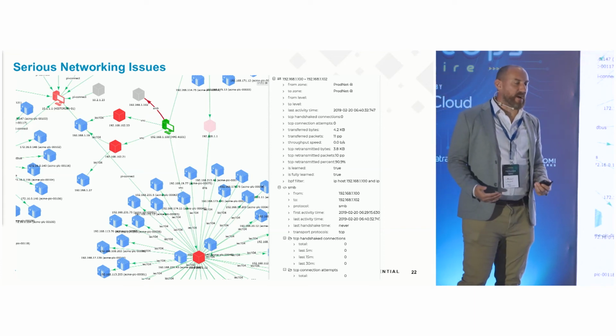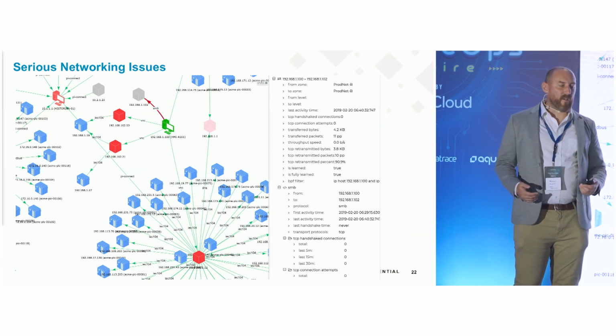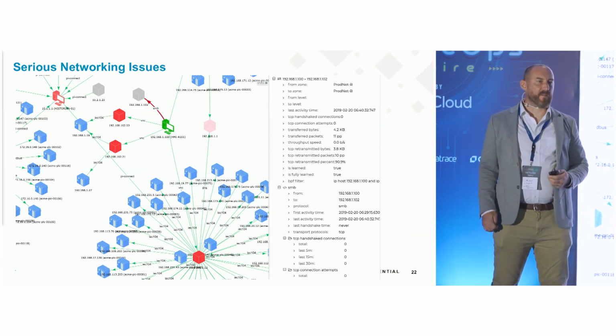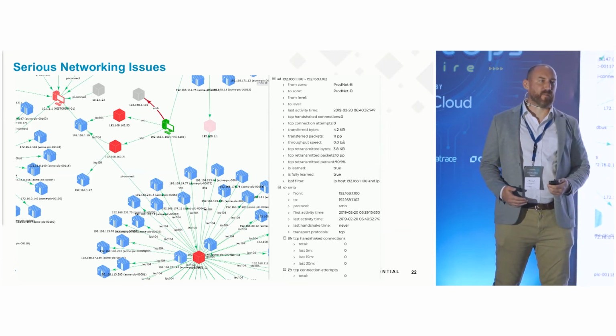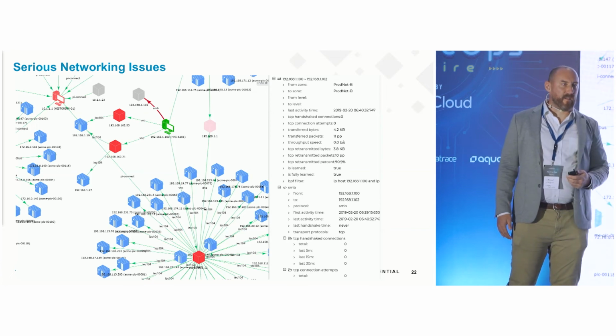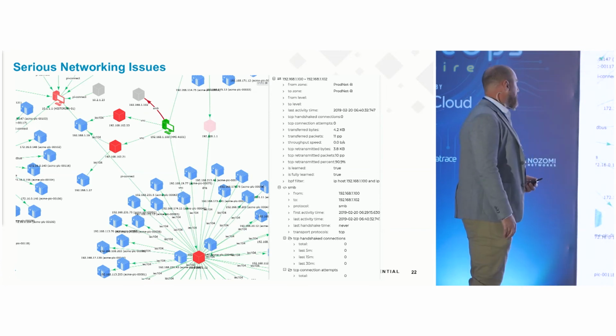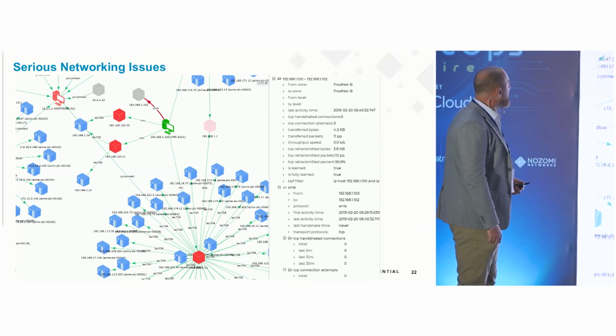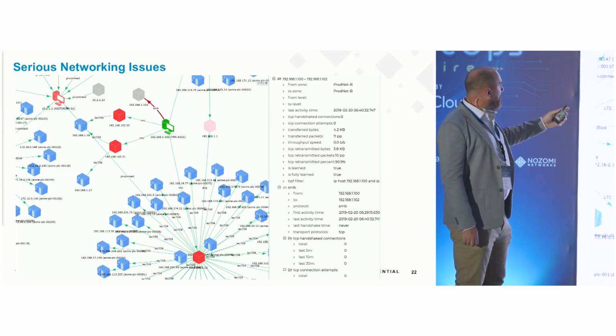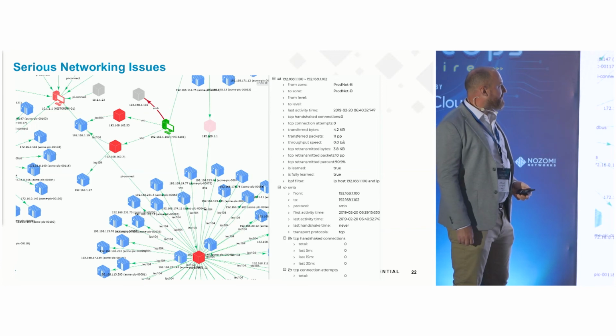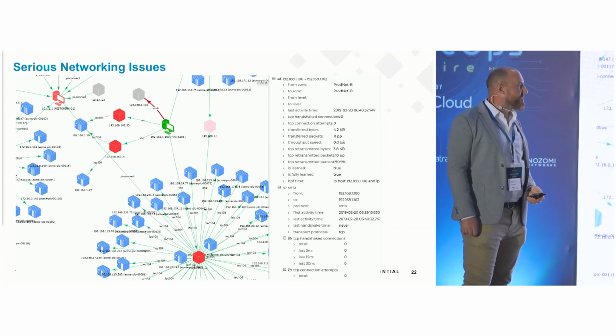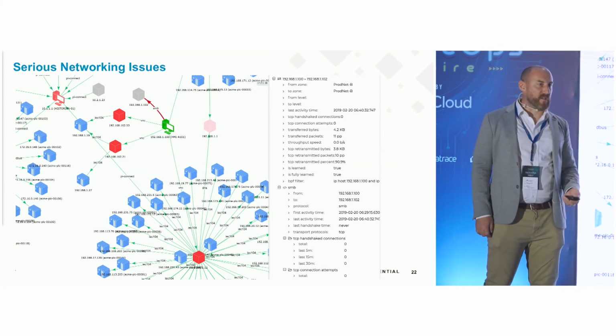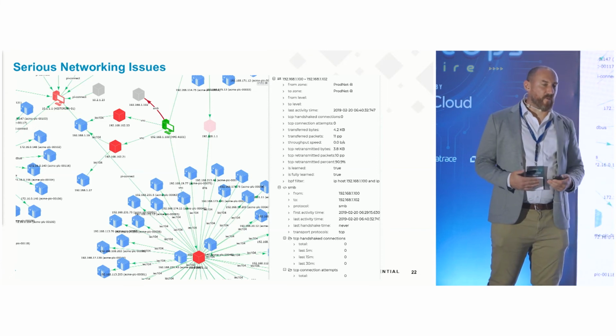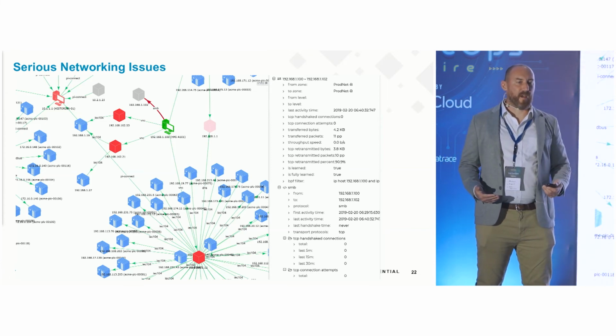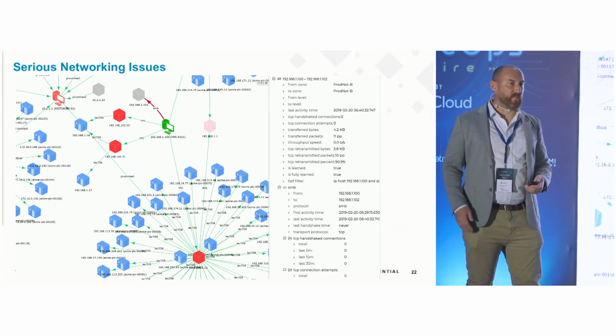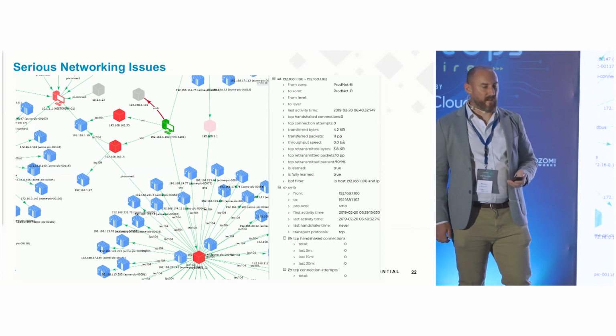Networking issues. Again, not really a cybersecurity concern, but these are networks that aren't typically monitored by standard tools, so these types of things can get missed. They also don't get updated very often, so the cables may have been laid 20 or 30 years ago, and it could be basic cable degradation, or too many packets on the network. These are usually 10 meg or 100 meg links. In this example we see a communication link with a TCP retransmission rate of 90.9%. Could be a bad cable, could be something going on with the host or the network card, but it's something we weren't looking for from a cybersecurity perspective—we were able to help a customer uncover a problem they wouldn't have identified otherwise, because you can't use Nessus scanners and tools like that within these industrial networks.